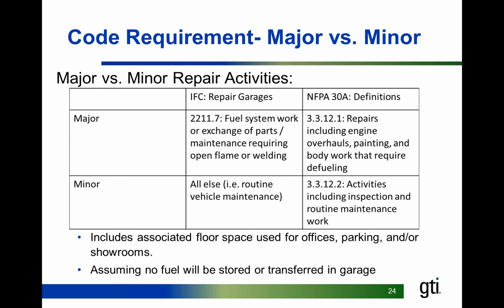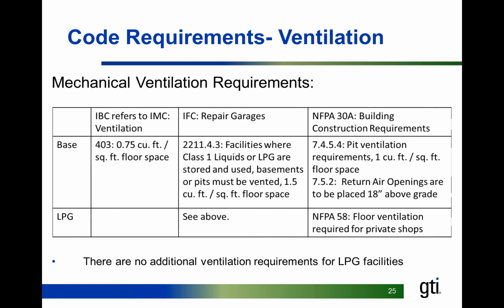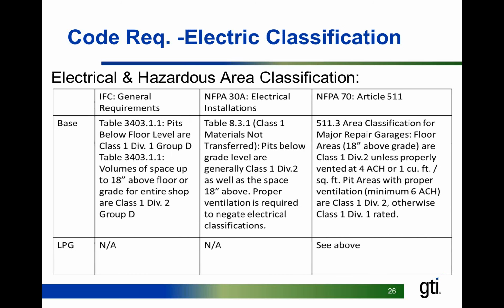It's the same 18 inches from the floor up where your real hazard areas are. There are some smaller differences, but it's much more similar in nature, and the codes are more similar in nature to gasoline and diesel. Ventilation requirements, typically there are really no changes for propane facilities as long as you have the base requirement. If you meet the baseline, it's typically the same. The electric and hazardous area classifications are very similar. Some of them, NFPA even mentions propane in some of the traditional fuel areas.